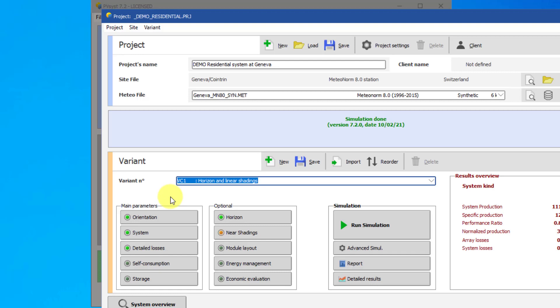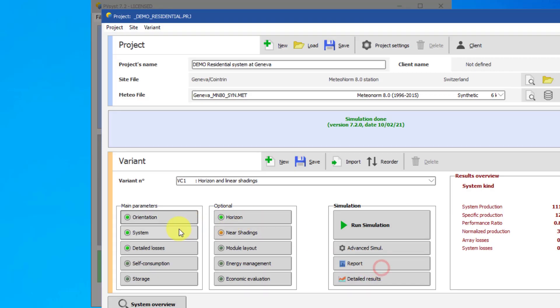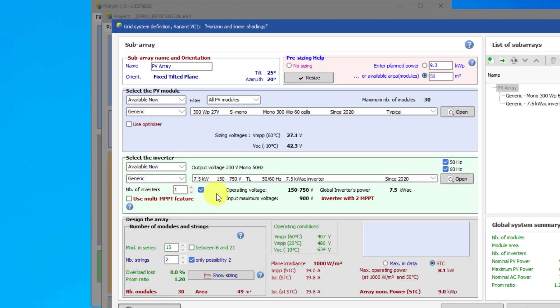When defining a variant, the first operation is to define the orientation of your PV array. There are many different orientation modes to choose from, including tracking. Then you have to define the system configuration. In the blue frame, we can choose a PV module from the database. In the green frame, we define the inverter. The gray frame defines the array properties, i.e. the number of PV modules in series and the number of strings in parallel. Note the blue dialog box here. Throughout all of PVSyst, there are blue dialog boxes like this one that will display information relevant to the current windows.